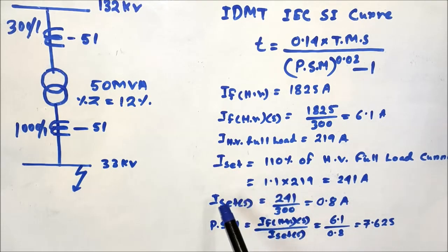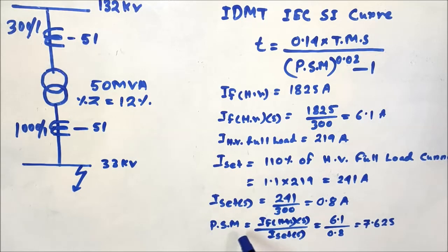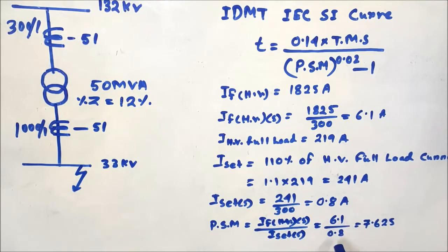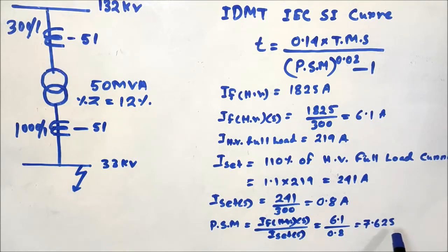The plug setting multiplier (PSM) for the HV overcurrent relay is the fault current sensed by the relay divided by the current set value. The fault current sensed is 6.1 amperes and the current set is 0.8 amperes, giving PSM = 6.1 / 0.8, which comes to 7.625.